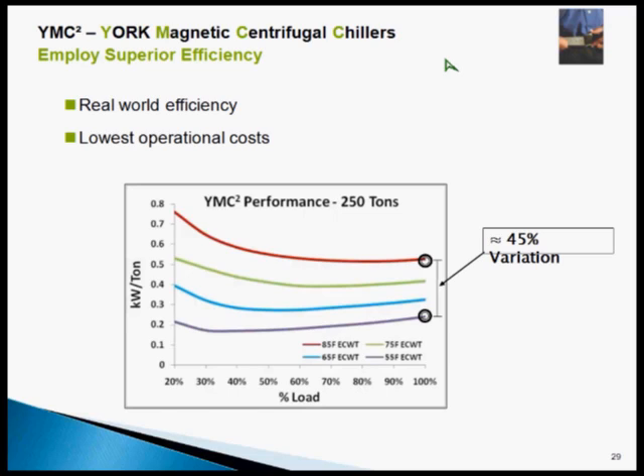So what do you think the kW per ton of a chiller should be, like if you spec'd it out? Let's make an engineering spec. It's a tough question for this crowd because a lot of you aren't really in that business. But I'll call on Jet. What should be the kilowatts per ton of refrigeration typically used in a spec? 1.8. Yeah. Most engineers are going to be anywhere from 0.7 to 1, depending on the system, depending on what equipment is hopefully going to be provided in proposals.